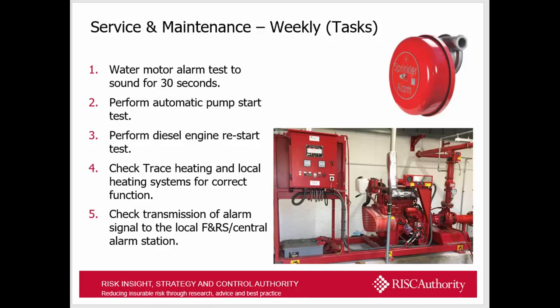Weekly service and maintenance tasks — things you physically have to do — include: running the water alarm gong for a period of 30 seconds; performing an automatic pump start test; doing a diesel engine restart test; checking trace heating and local heating systems for correct function. If you have a diesel pump in a pump house, that pump house must be maintained at 10 degrees C. Trace heating panels need to be tested weekly. Any transmission of signals to the local fire and rescue service or central alarm stations should also be checked. These are tasks required of site staff.